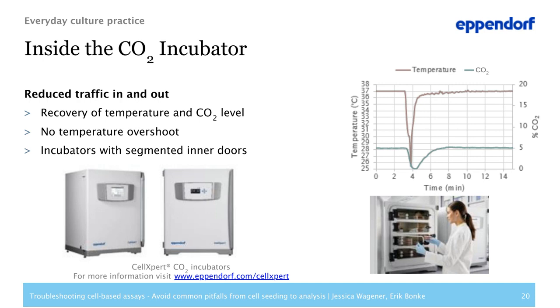The CO2 incubator also plays an important role in cell maintenance. Every time the door is opened, the atmosphere inside gets disturbed — temperature, humidity, and CO2 level all have an influence on the cells. It is good advice to reduce traffic in and out of the incubator as much as possible. An incubator with split inner doors helps keep the atmosphere stable because the area that is opened is smaller. In the Eppendorf CellXpert incubator, both CO2 and temperature reach their set point again in less than five minutes after a door opening.